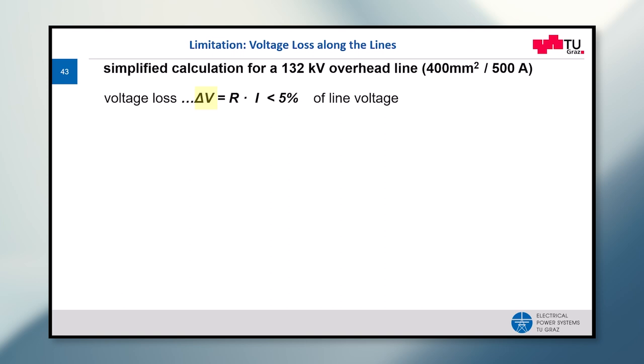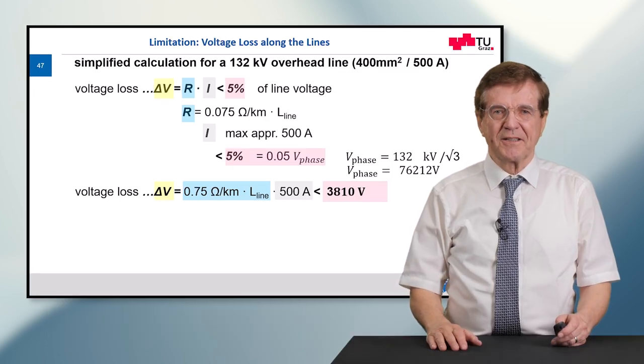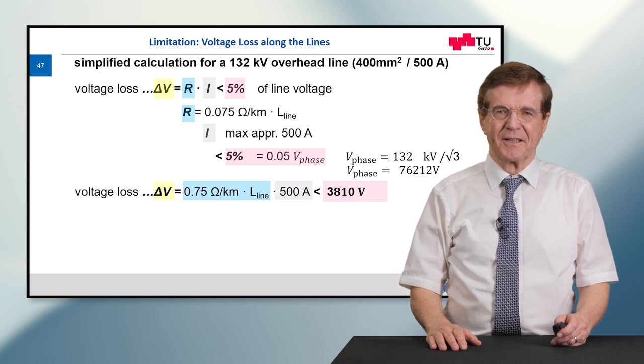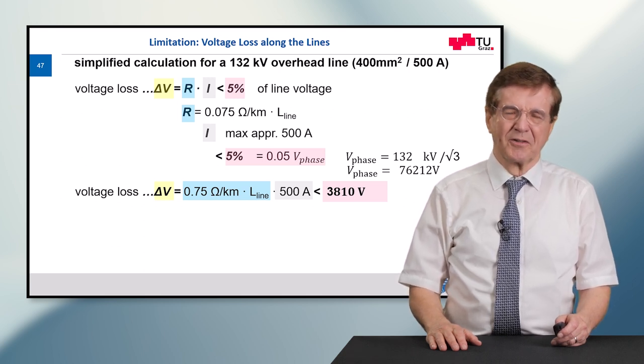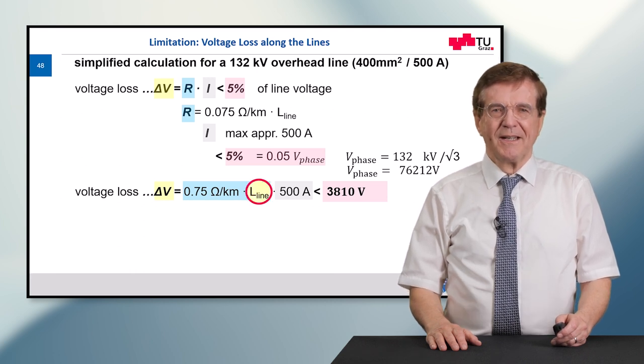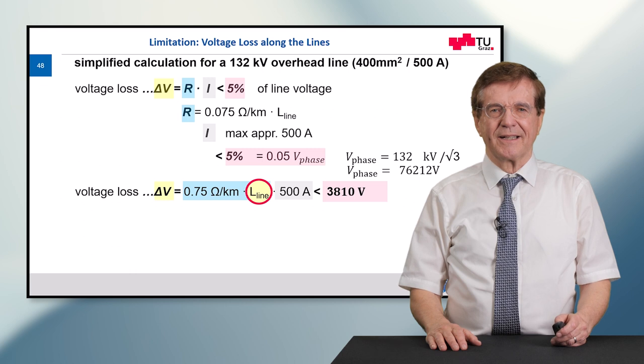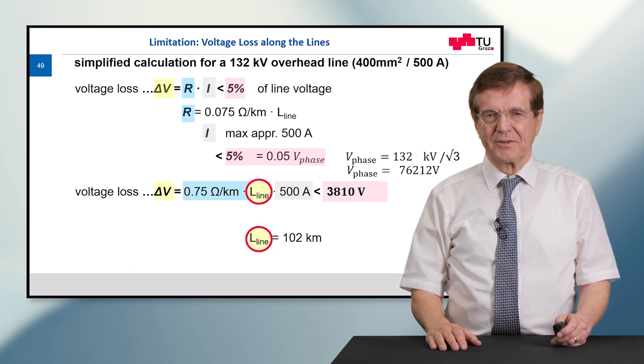So the voltage loss across a line should be limited. So for example, we do not want to lose more than five percent of the voltage seen from the input to the output to the end of the line. And therefore, this means we can calculate now with these figures. The resistance depends on the line length. You see at the right side there is L line. This is the line length. The current is somehow always, as you saw, like 500 amps. And this five percent of the phase voltage can be transferred into this voltage of no more than 3810 volts. Now we can from this equation determine the line length, and the line length here results in 102 kilometers.